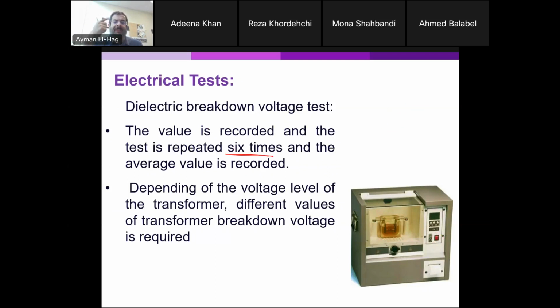However, if you just repeat the test every time, because of this contaminant, it will reduce the value, not because the quality of the oil is bad, but because now you are introducing a contaminant coming from the test, because we have a flashover. Okay? So what we have here is a magnetic stirring element that, after the test is done, starts to rotate, to circulate the oil, and to disperse this contaminant so that it's not concentrated in one point that will affect the result. And again, this is done automatically.